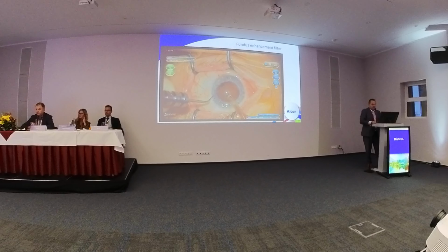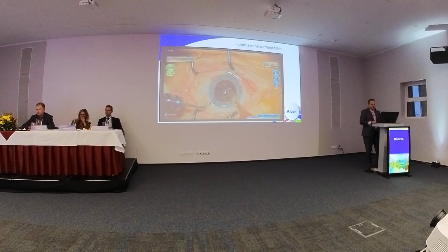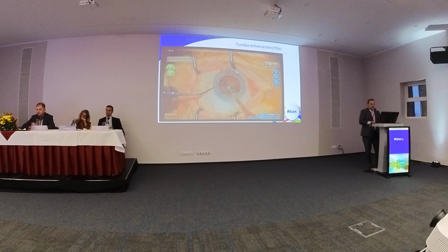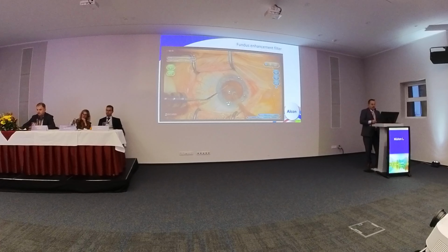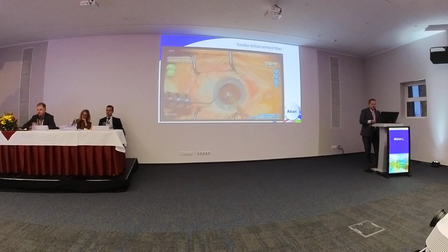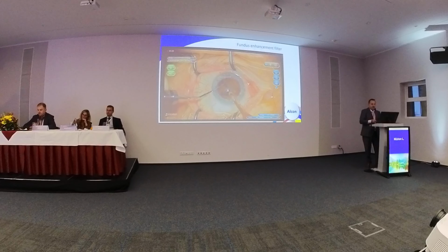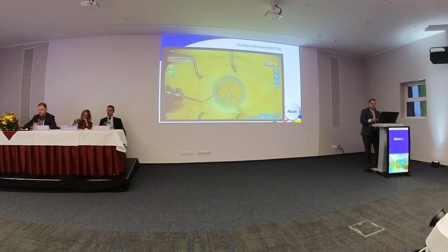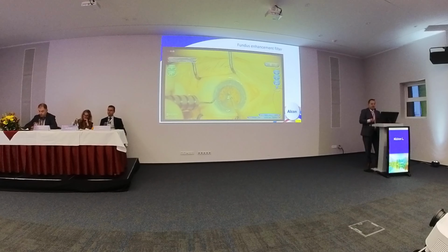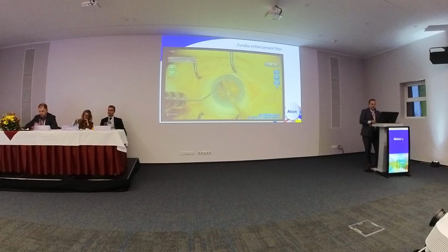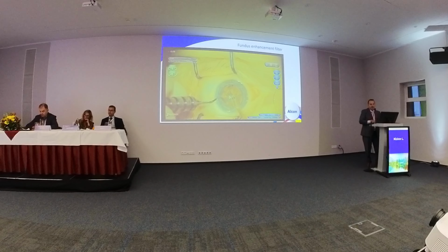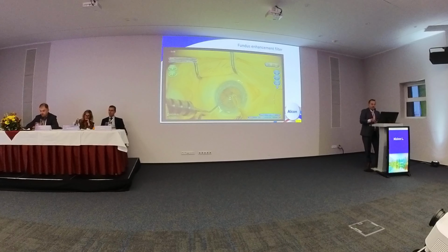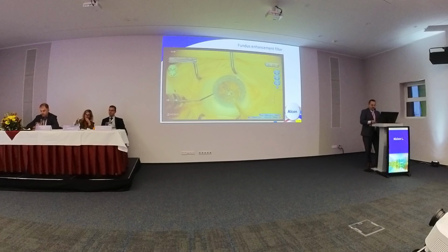So this is an example of the fundus enhancement filter. You might see the regular image and the appearance of the lens, and while we are chopping the lens, normally we lose the visibility. And when we engage the enhancement filter, we suddenly start to see transparent pieces. Why is that important? Because I can judge how deep I can go with my instruments, and ultimately it provides me with a safer surgery.